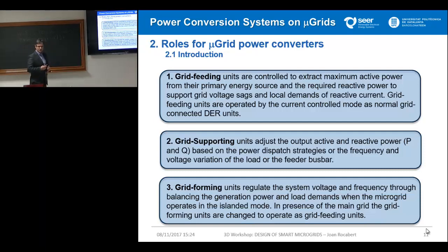Okay, the grid supporting converter totally or partially adjusts its operating point as a function of the condition of the microgrid or the grid. Okay, so if the system is working under frequency, the grid supporting converter injects more power in order to accelerate the grid and restore it to its original point. Okay, and the same for the reactive power. Okay, later on there is also the grid forming converter.